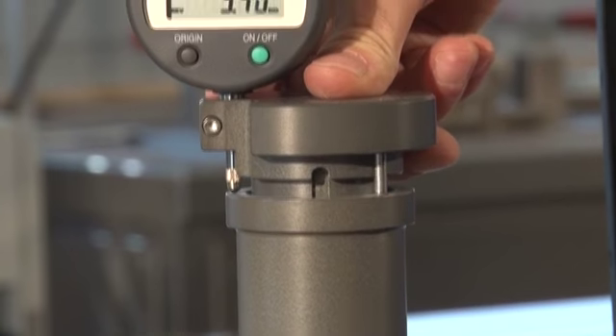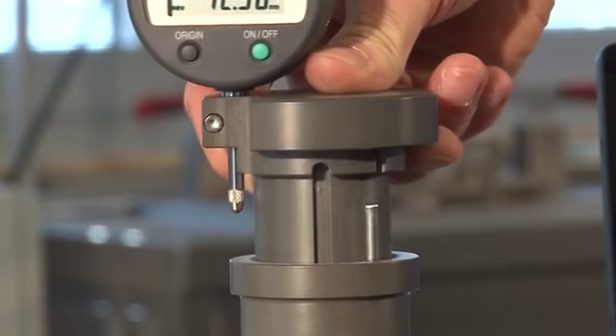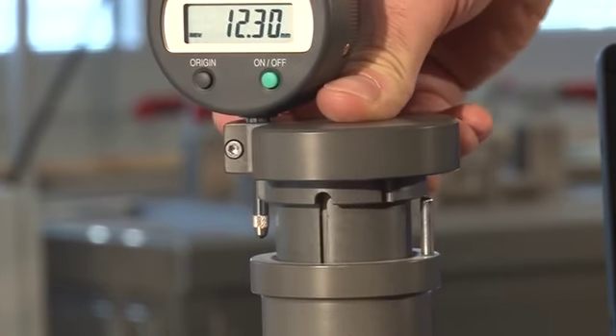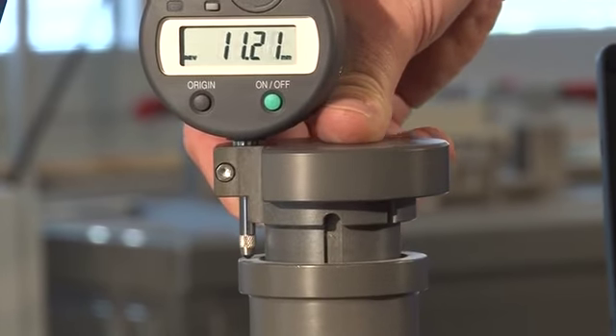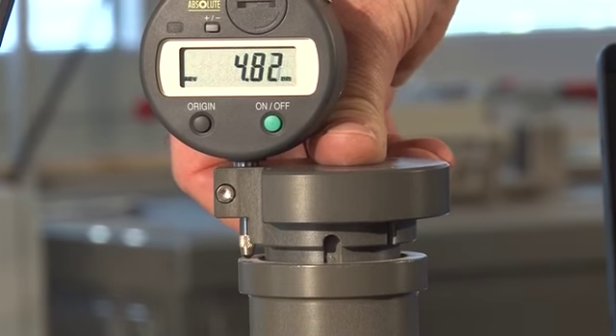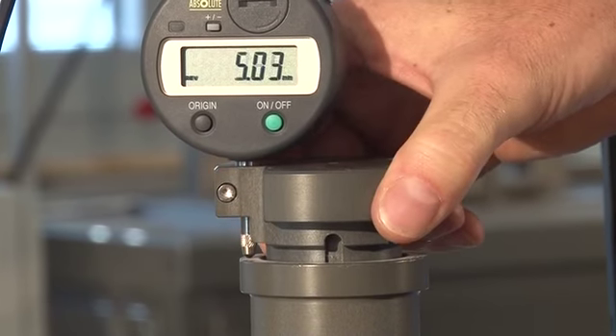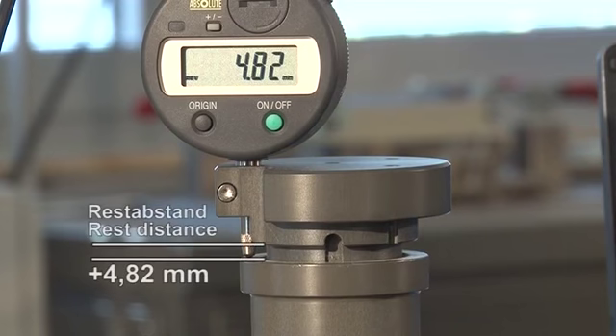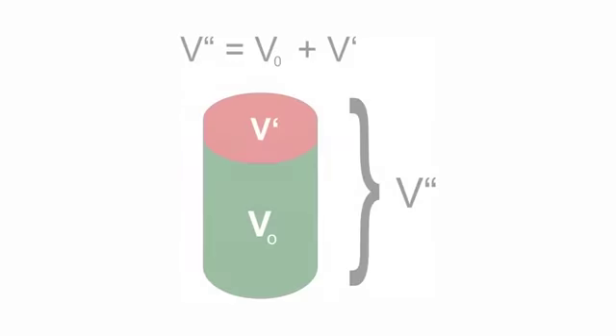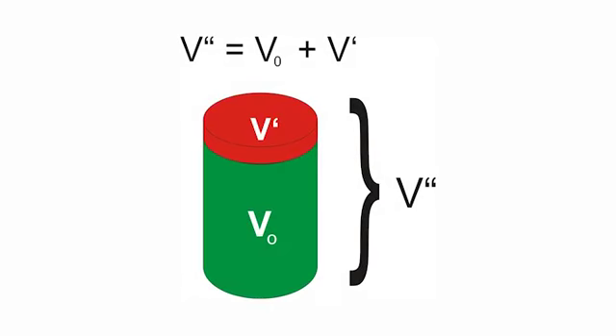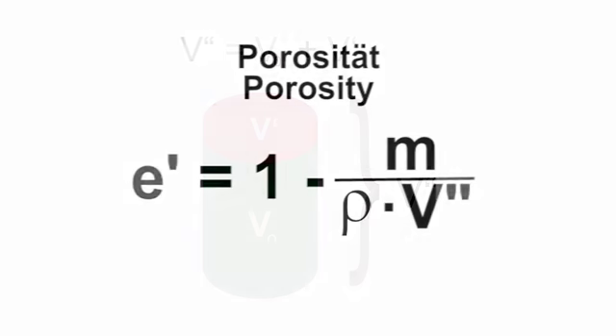In this example, the remaining distance of the sample is 4.82 millimeters due to too much sample weight as a result of incorrectly assumed porosity. However, a new cement bed does not need to be prepared. The additional volume V bar is calculated and the old volume is added so that V double bar is the result. The actual porosity can be determined with equation E.